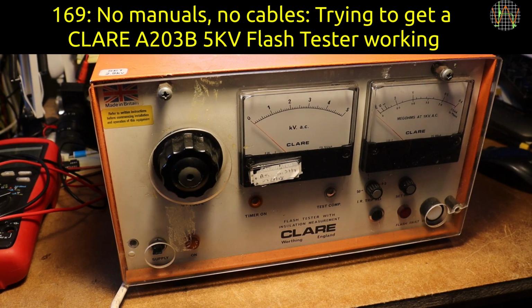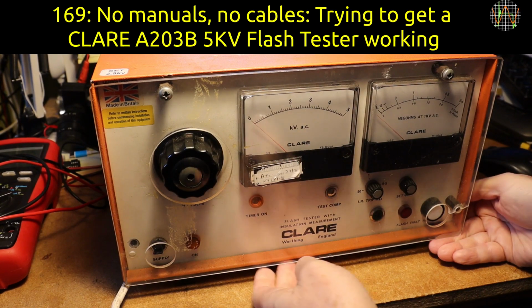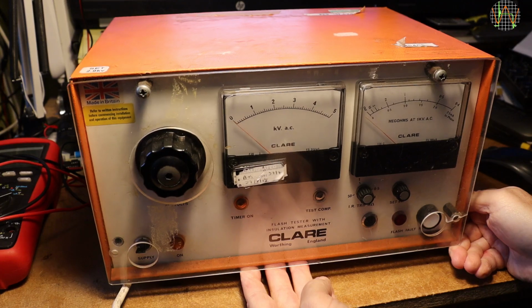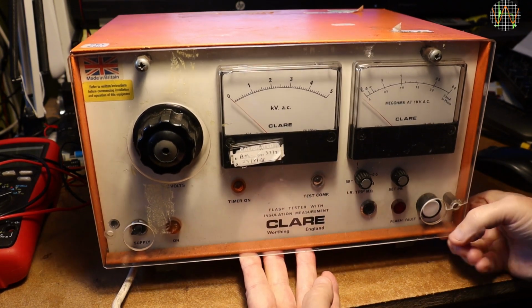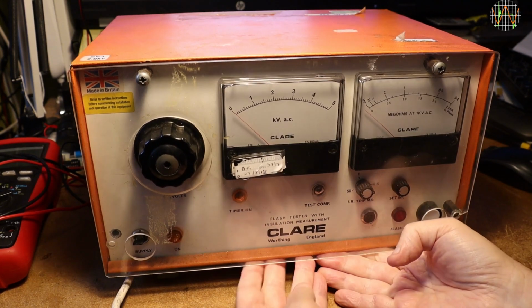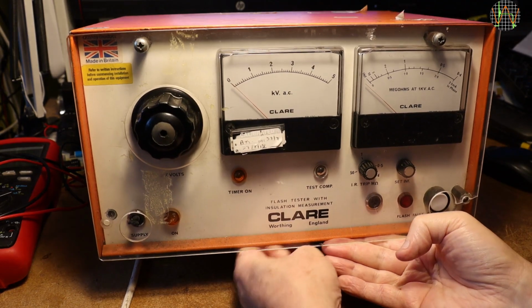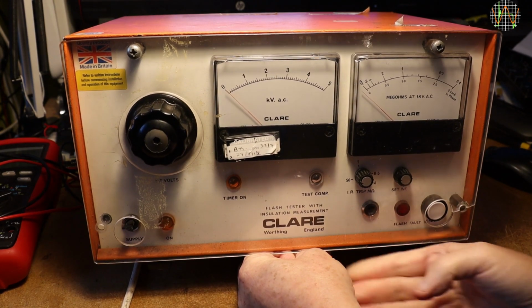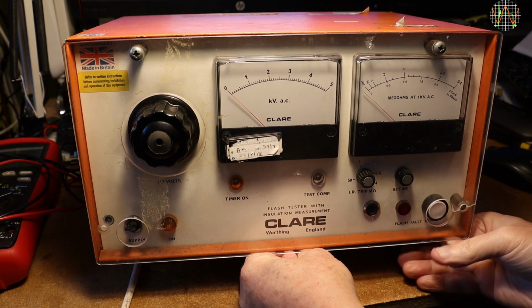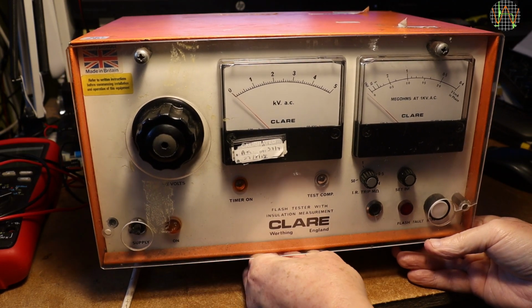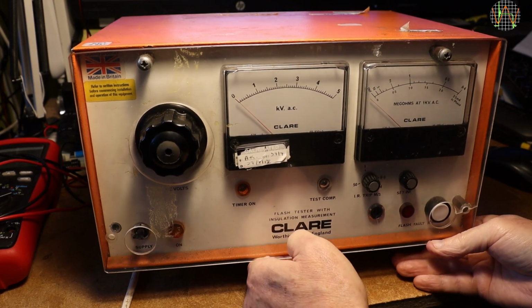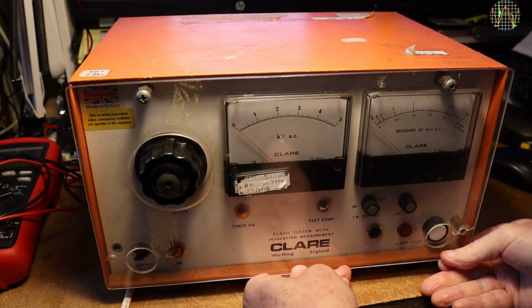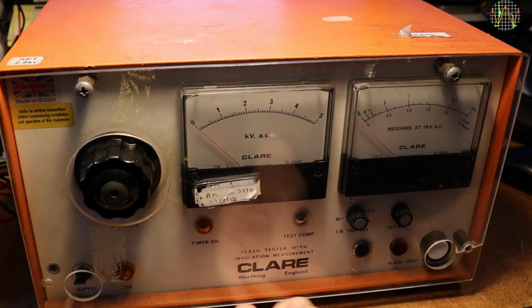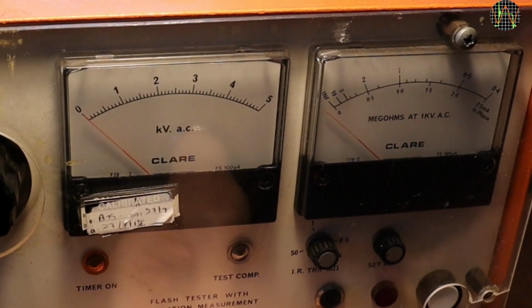Hi there, this is a rather unusual and heavy piece of test equipment that just arrived on my bench. It's a CLARE flash tester A203B with insulation measurement capability. It is extremely heavy, about 20 kilos, and someone has put a transparent plastic shield over the front, either for electrical safety or to prevent unauthorized changes of settings, quite possibly for both reasons.